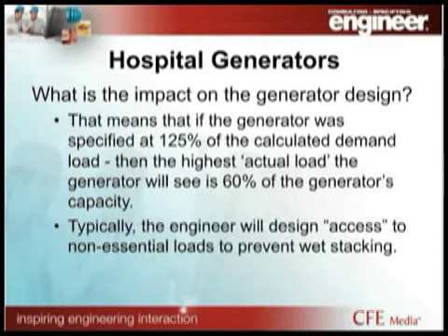So how does this impact the engineers that I have on the call, and how do they work around it? Hey, I've added up my life safety and my critical loads. How am I going to make sure that when they test that generator every month, I'm not only loading it up to 20%, that I'm getting more load to it? Well, one of the things is, as suggested, parallel two smaller generators, as long as you're still keeping the size large enough to permit that coordination to happen on your selective overcurrent protection.